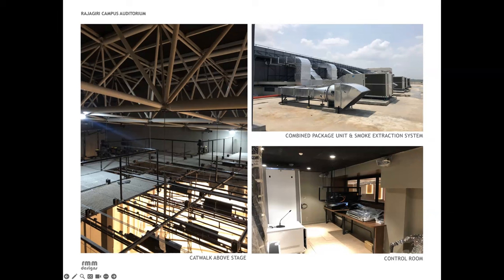So this is an exclusive exhaust duct. The damper over here, a damper is basically like a shutter, closes over here. The damper for this duct opens, the return air comes over here, and this exhaust fan also starts automatically when there is a fire alarm. So your return air, when there is a fire alarm, instead of going back to the AHU, automatically starts getting exhausted from this exhaust duct. This is a very important requirement which all of you should keep in mind.